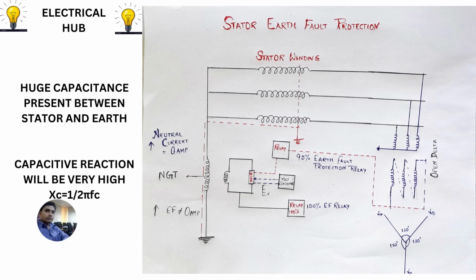Because a huge capacitance is present between the stator winding and the earth due to the insulation of the winding, and also the signal injected by the voltage injector is of very low frequency. So the capacitive reactance will be very high, because Xc is equal to 1 by 2 pi fC.